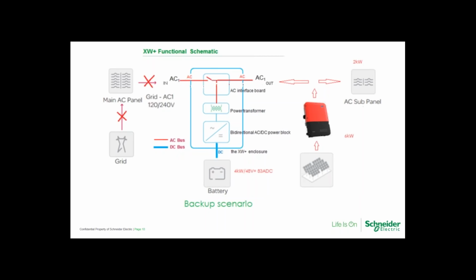So here we can see what happens in the backup scenario. The internal transfer relay is open. The connection to the grid is completely isolated. And we are grid forming from the battery, and we're fooling the grid tie inverter into thinking the grid is still there, thereby allowing that PV to flow.